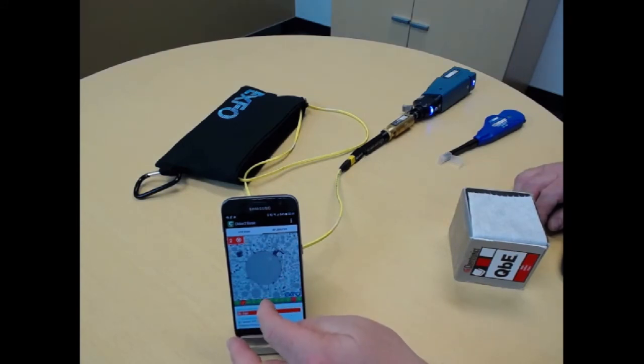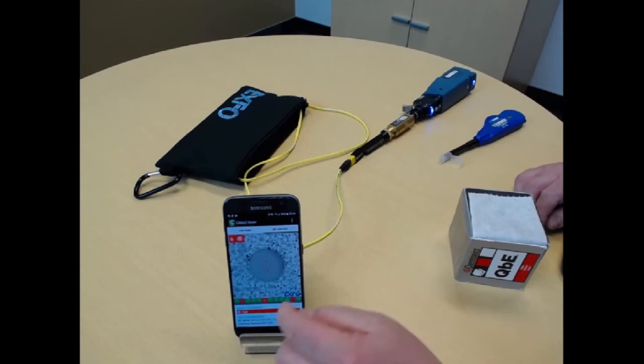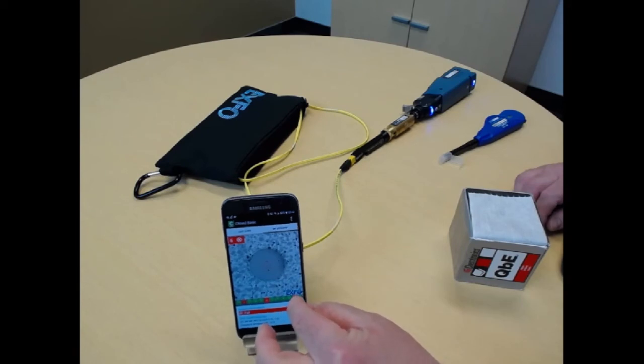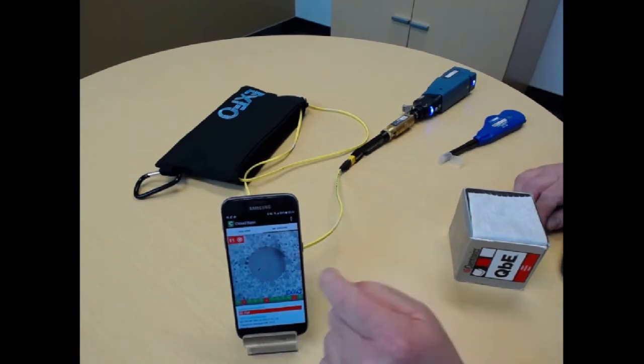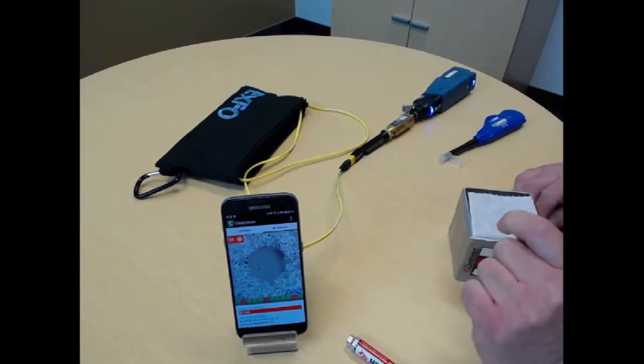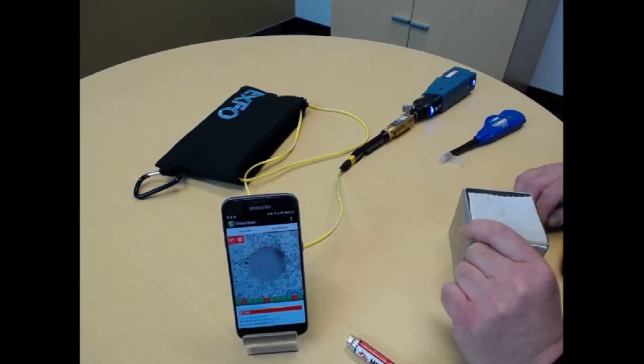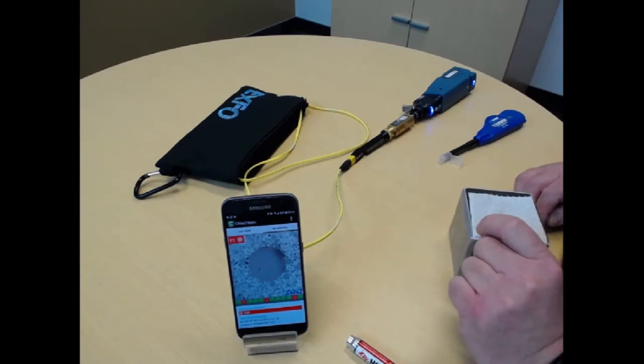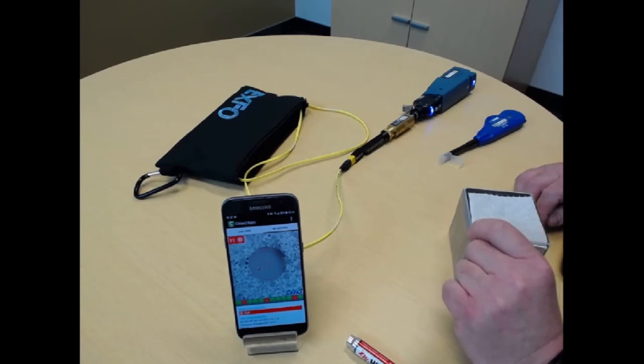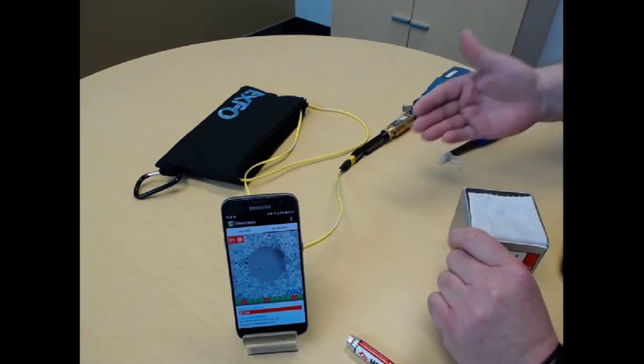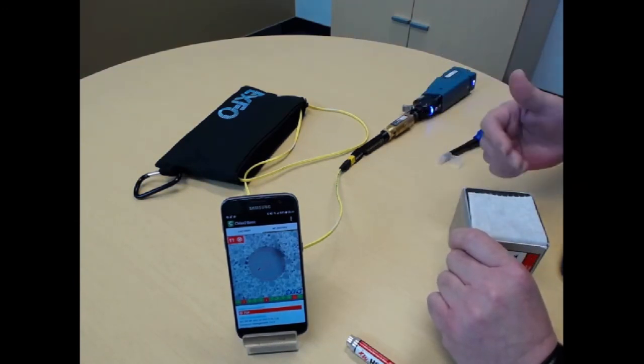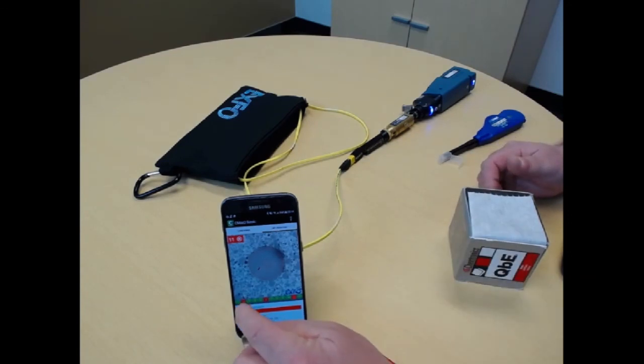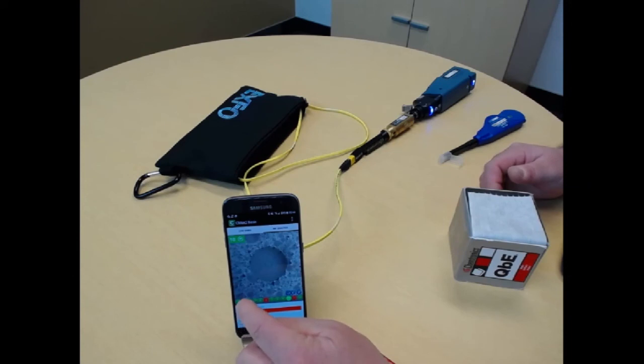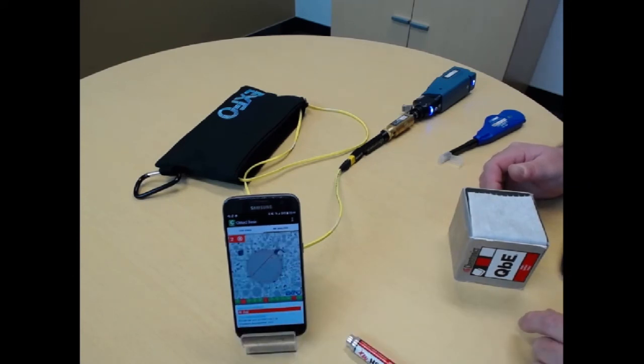So now I go to 5. My dirt is outside my clad. It may be a spot. And here, it's still dirt outside the core section. So it's not a disaster, but because it's a rather big piece of artifact or dirt, I'm going to have a fail on that one. So I can re-clean this connector using again the wet dry, but as I said, never expect it to polish the scratch on this number 2 fiber.